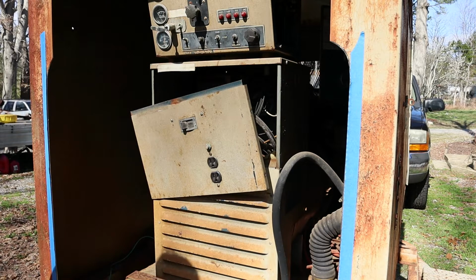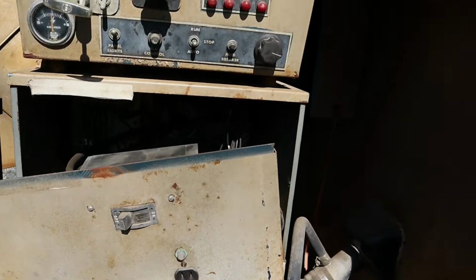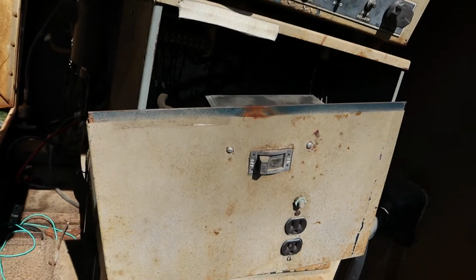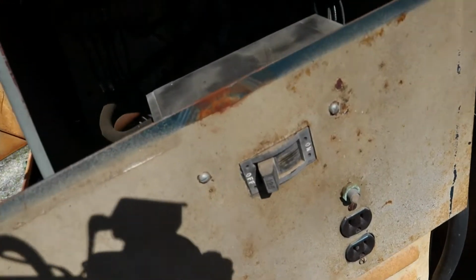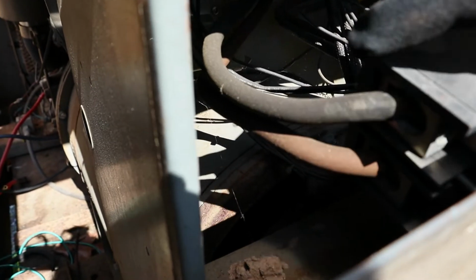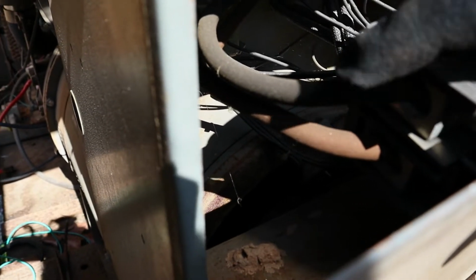Let me get you in there. So here's the main breaker. It's 125 amps, 240 volts. These are the output wires right here, and there's only 2 of them, so that means it's not 3-phase.